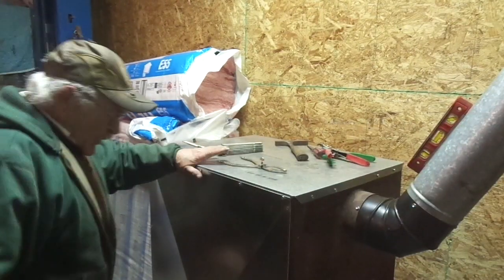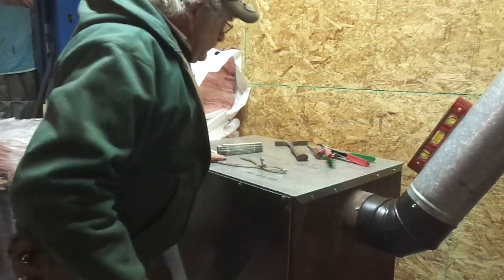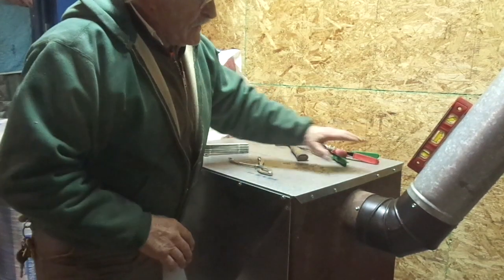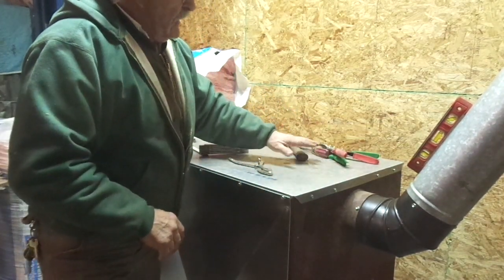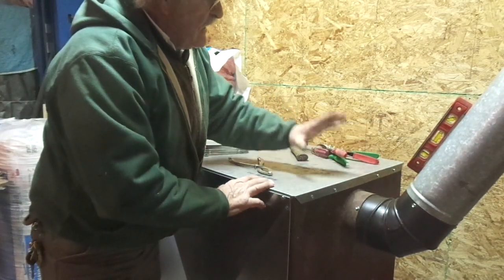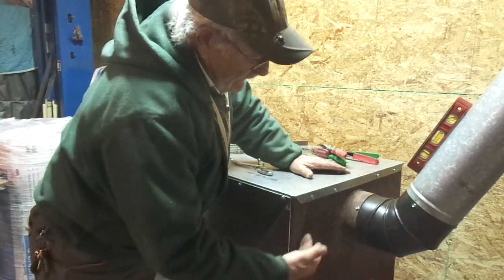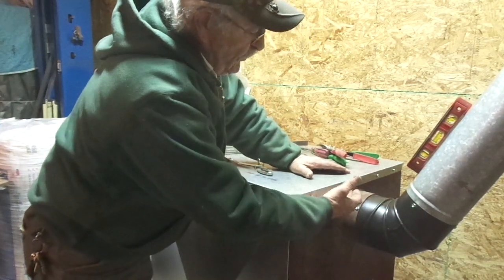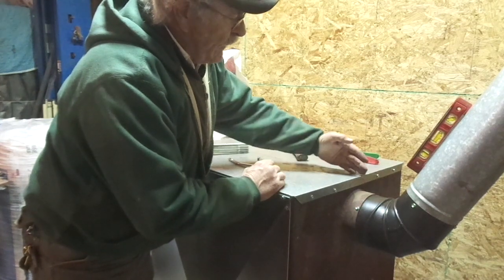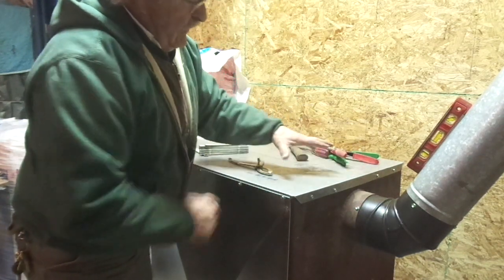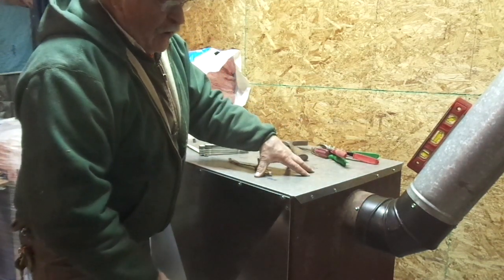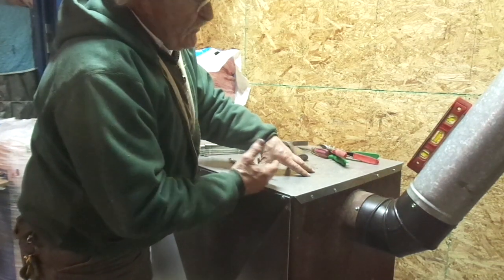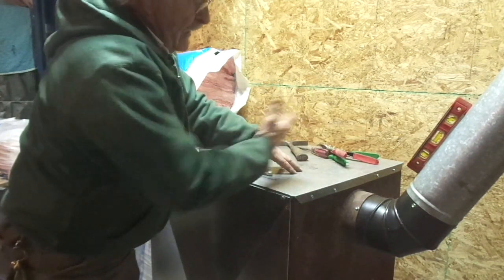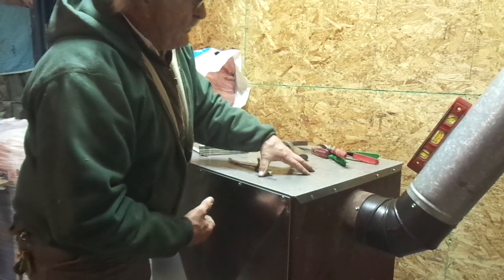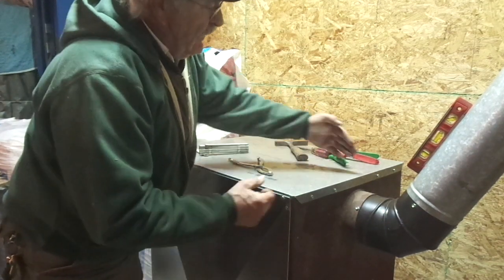And when you're ready to cut your holes, you have to think about what that heat exchanger looks like in here. A lot of times it's just a square box. This particular one comes up and angles over, and has somewhat of a pointed top right here dead center. If you cut a hole back in this corner, how are you going to get a mixture of air from the surrounding area of the heat exchanger if you cut along this side or that side of that center point?